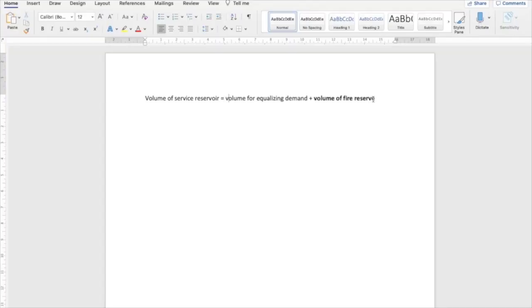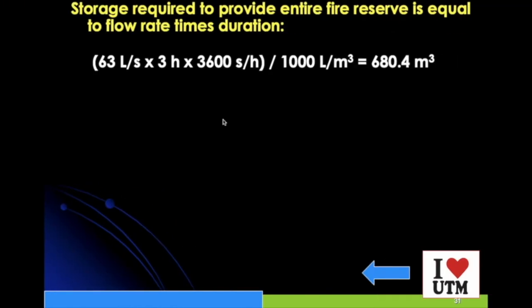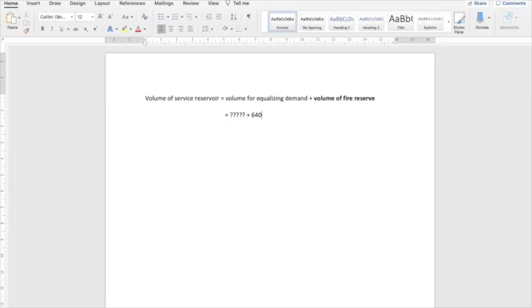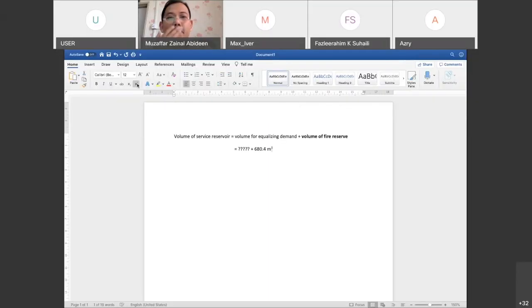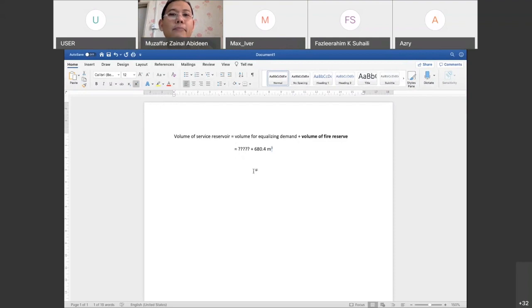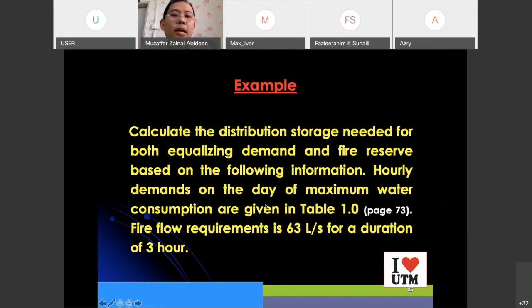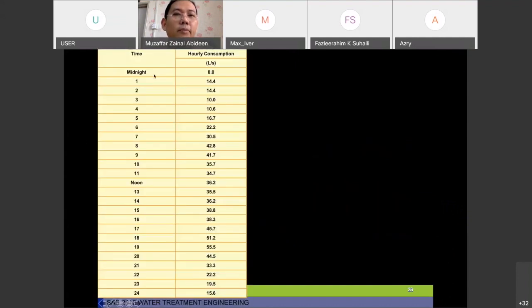We already got that value - the fire reserve is 680.4 meter cube. Now we need to find out the equalizing demand. How do we do that? This is where you need this table.